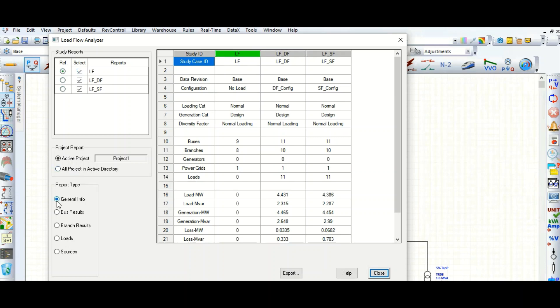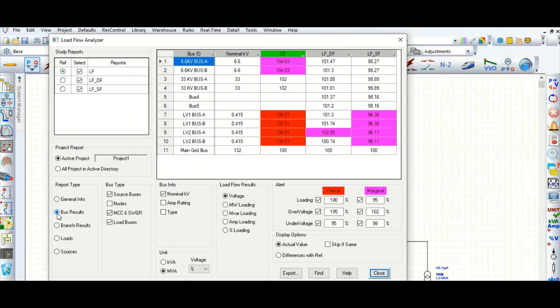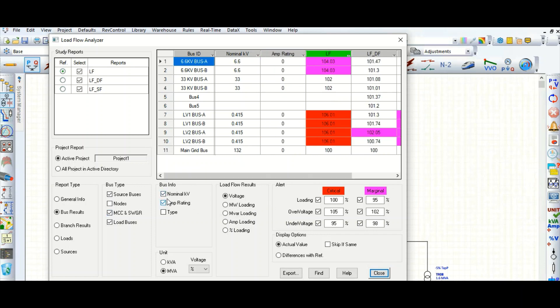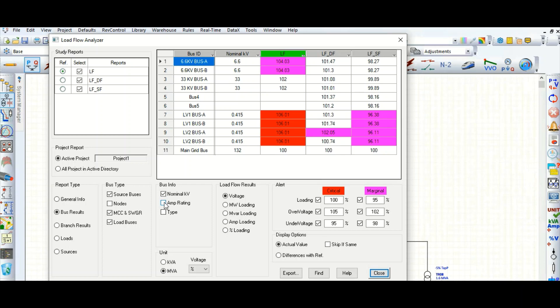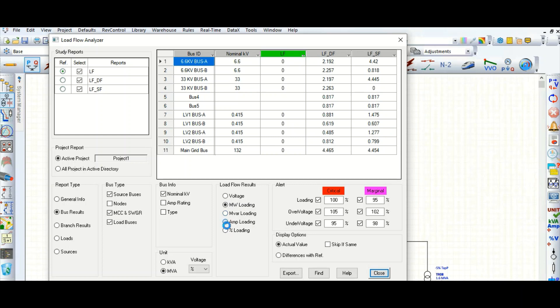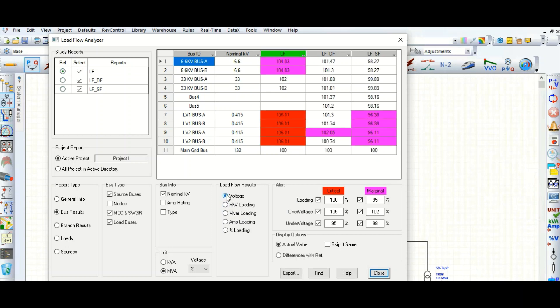Next are the bus results. You can select the bus type — source bus, node MCC or switchgear, load bus — and check or uncheck as needed. Under bus info you have nominal kV and ampere rating. The ampere ratings are not provided in our model, so they are not showing. In load flow results, you can get bus voltage, megawatt loading, ampere loading, and bus loading percentage.